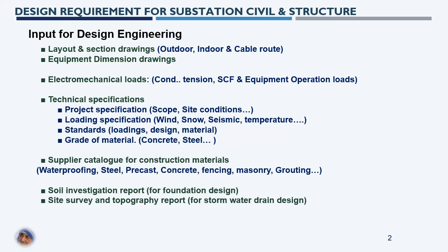Next is the technical specification. Generally, technical specifications can be classified into four categories. The first is project specification, which provides information about scope and site conditions — whether the site is in a particular terrain category, a low-level area, a water-prone area, or a hilly area. The second is load specification — what loads should be considered for civil and structural design, such as wind, snow, seismic, temperature, and, for industrial substations, dust load.